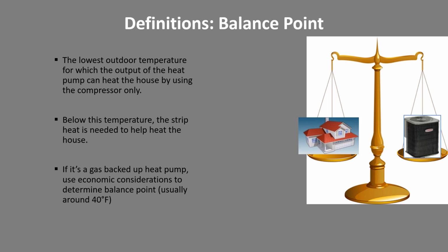We often hear the term balance point, and it's simply defined as the lowest outdoor temperature for which the output of the heat pump can heat the house by using the compressor only. Below that temperature, the strip heat is going to be needed to heat the house. If it's a gas backed up heat pump, usually it's economic considerations, price of gas versus the price of electricity, etc. Usually it's down to 40 degrees.